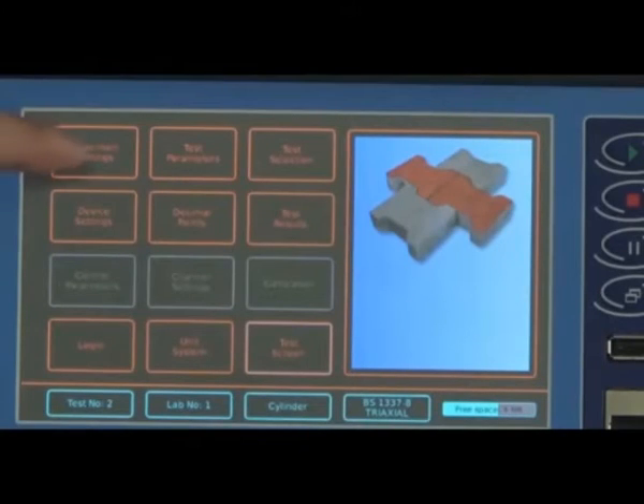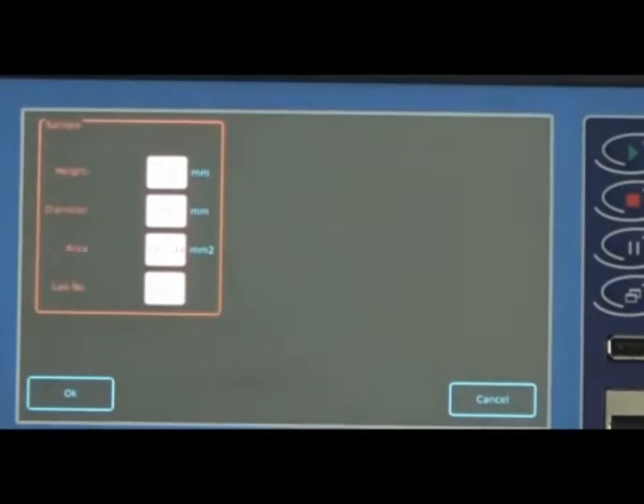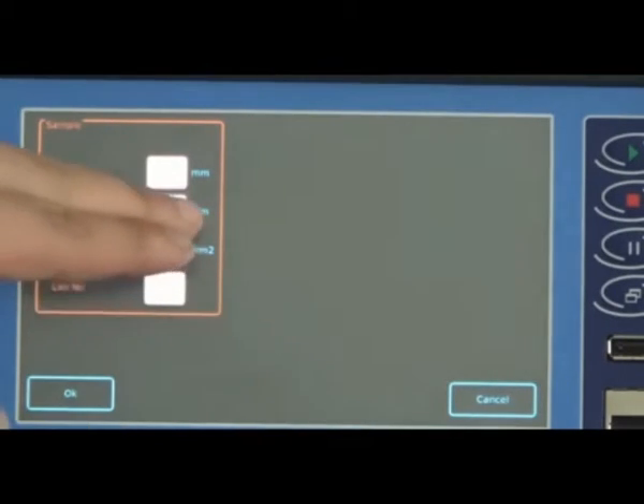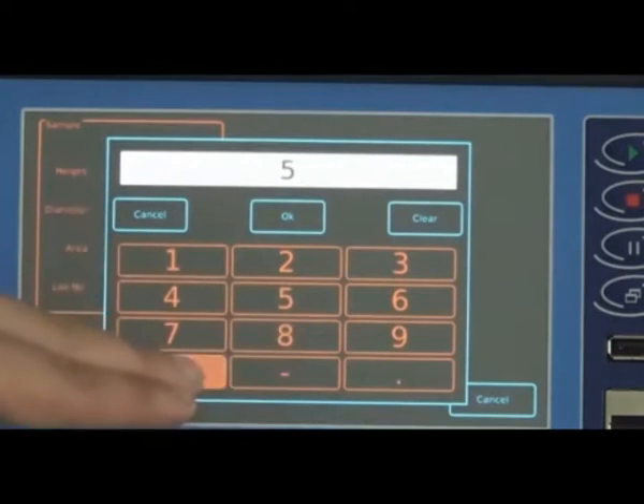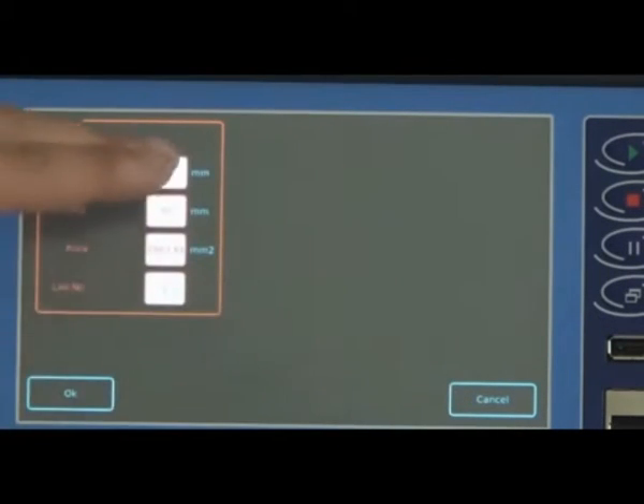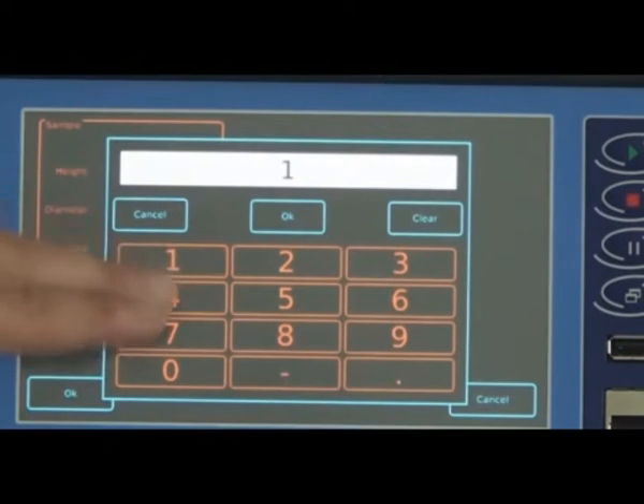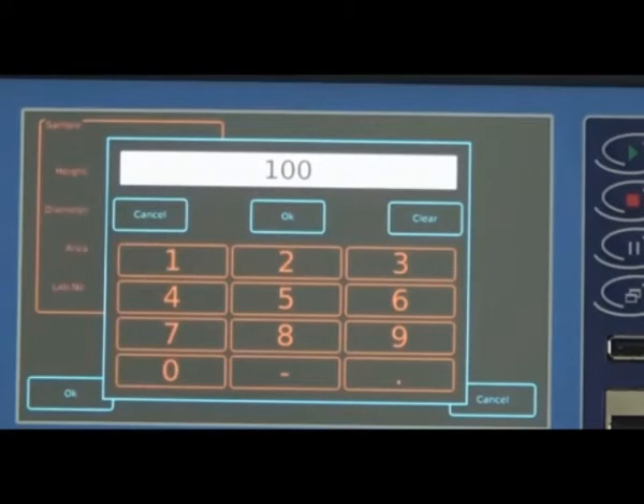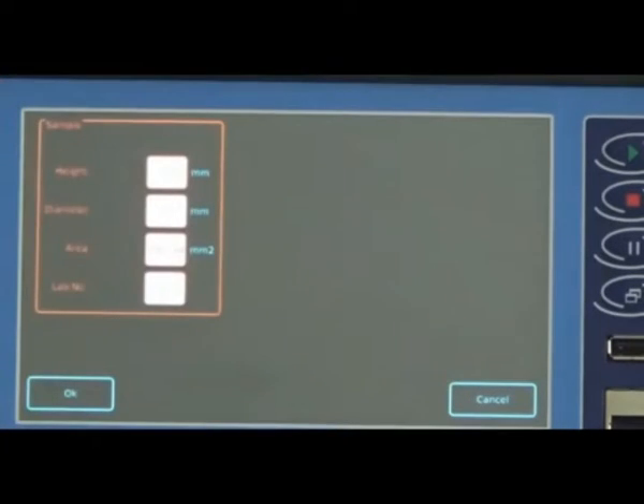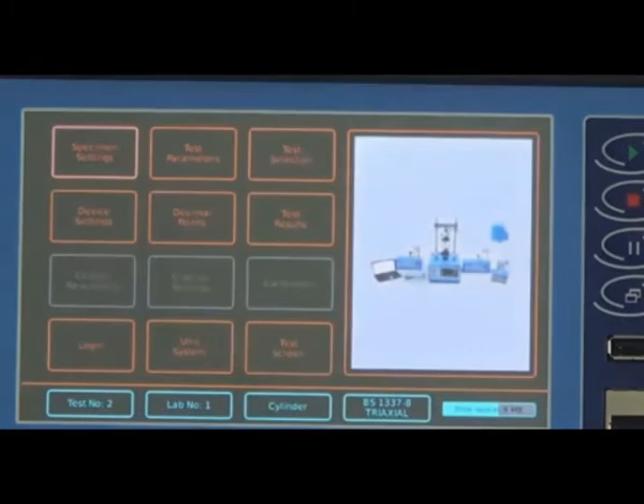The first menu on the screen is specimen settings. Since we have used the 50 mm diameter of specimen, we are going to enter this diameter as 50 mm. And the height of our specimen is 100 mm. As you can see, the area is calculated automatically. And assuming that this is the first test, we are entering the first lab number 1. And by entering OK, we are out of this menu.